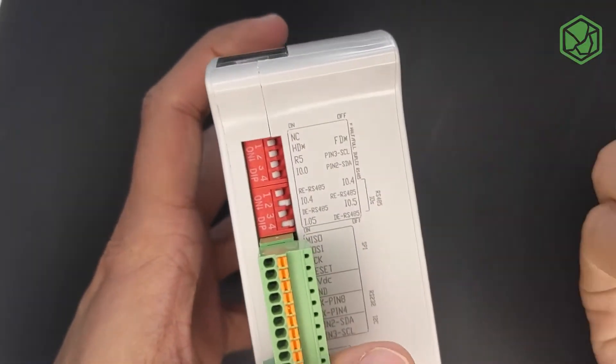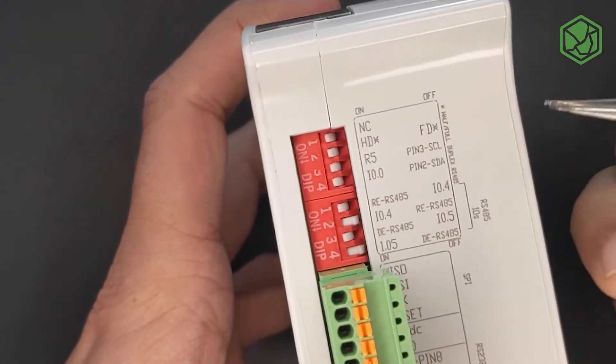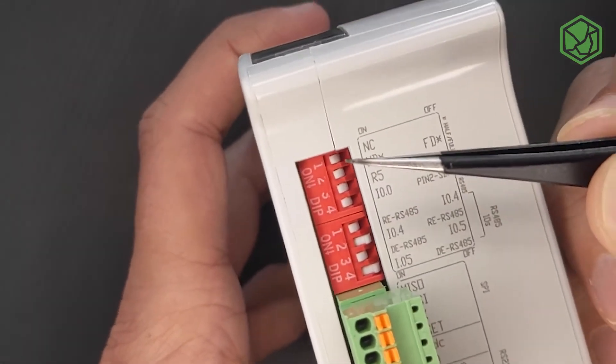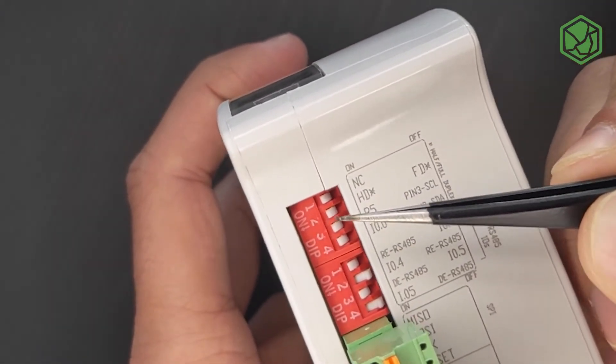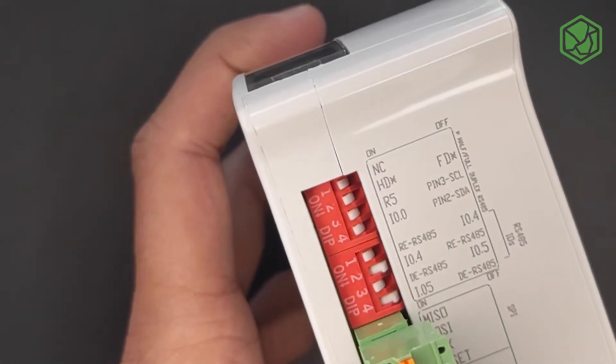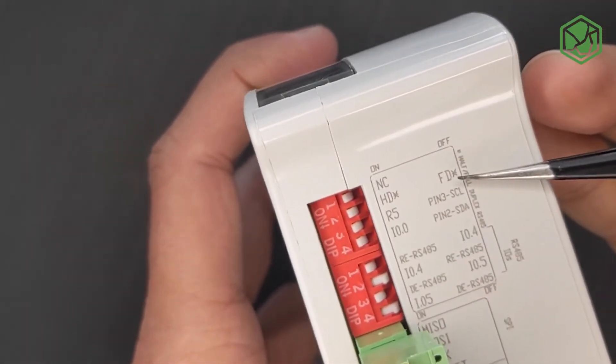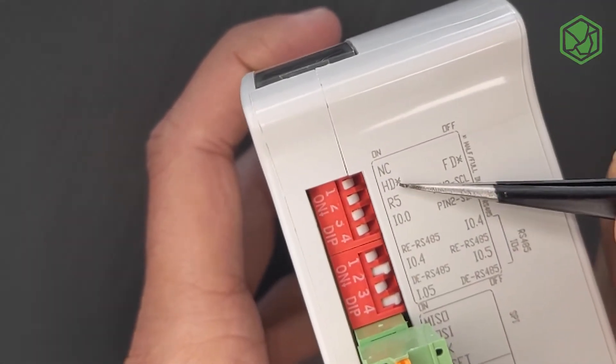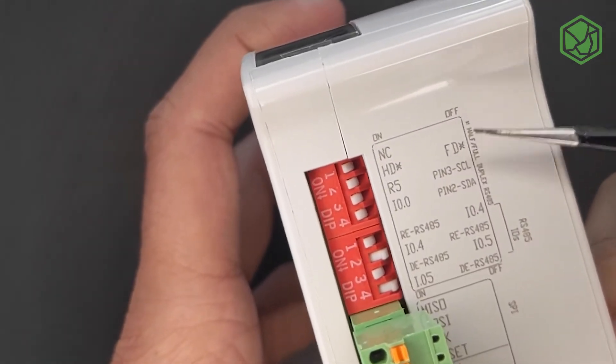Furthermore, for RS-485 communications, on the right zone you will have two blocks of DIP switches. Switch number two of the DIP switch belongs to the half duplex or full duplex configuration. If it's turned on, it's half duplex. If it's turned off, it's full duplex.